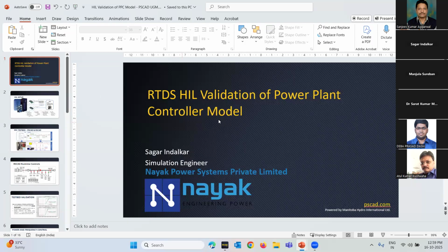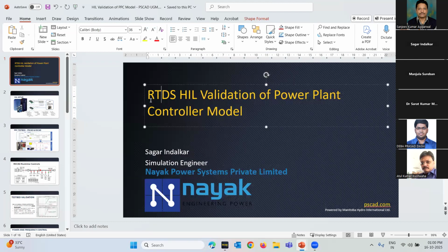One of the most important validations is validation of the power plant controller model, the PPC model, which you have built in PSCAD. That model must be validated before you can say that this is the actual representation of the physical controller. This can be performed using RTDS. RTDS stands for real-time digital simulator. It is also an EMT simulator which can perform time domain simulation in real time.